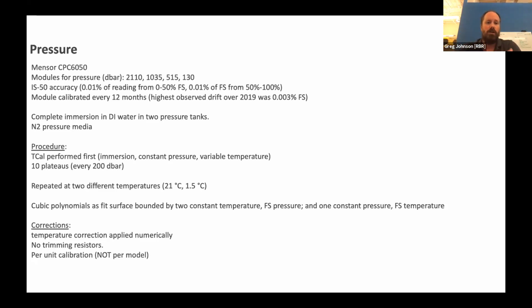We calibrate all of those modules for all of our different pressure controllers every 12 months to NIST standards. And if I just went and plucked the readings for 2019 for the last full year, the highest drift that we saw on any of those modules was 0.003%. So quite happy with those and their drift over the year. As I said, we're using the pressure controller to pressurize nitrogen.